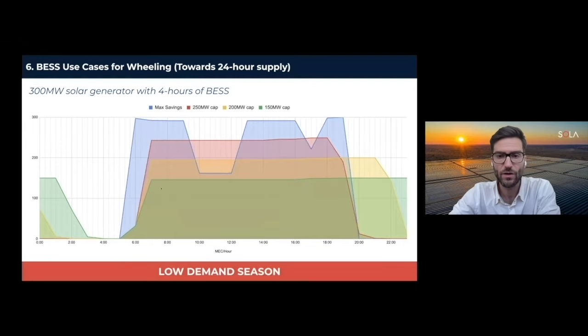This is effectively during the winter months, but if you go to the summer months, you get quite a lot more coverage as well. From a technical perspective, you can start to get up to 17 hours of effective solar power a day, which is with the 4-hour battery. Obviously, the larger that battery becomes, the more you can extend that. And what's very interesting about this is that all of these cases are economically viable, if I can say that. So you're still getting a substantial saving from this green profile, even though you're not necessarily taking maximum advantage of this arbitrage into the peak periods. Each of these cases is as it stands economically viable. You're getting a substantial saving by adopting these solutions. And as battery costs evolve and as general electricity prices increase, that picture is improving.